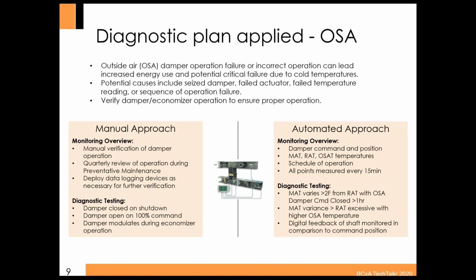The diagnostic testing that you're outlining in your plan is the analytics. It's the ongoing sequence that you would be testing to get the notification when you see abnormalities. So if you're seeing mixed air temperature varying from your return air temperature with the damper command closed, and that's happening for a period of time, then you're getting a notification. You're tracking how often you're getting that notification and the total duration of it, so you can get the magnitude and the priority of that issue.